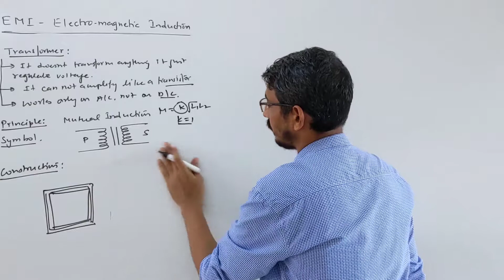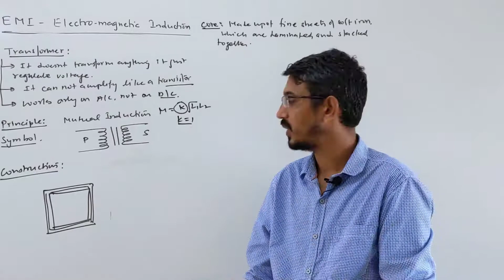Let me write a few words here. Your core is made up of fine sheets of soft iron, correct? Many fine sheets of soft iron, which are laminated. Why do we do laminations? Because there is a loss called eddy current loss. I will talk about this separately. So they are laminated and stacked together. Very fine sheets, not one thick material. Each sheet is laminated from the next sheet, and we just stack them together. That's called your core. I told you we use soft iron because we need a material of high magnetic permeability.